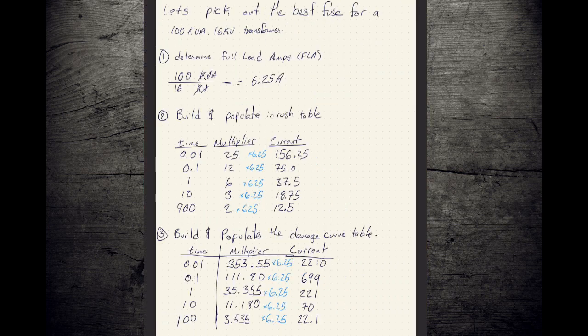Let's do an example. Let's go with a 100 kVA transformer this time. First step, figure out our full load amps. Second step, build our inrush table, just like we did before. We have our multipliers. There is no magic. You should just write these down and keep it someplace handy. If this wasn't a remote course, my test would be closed book and I'd make you memorize it.